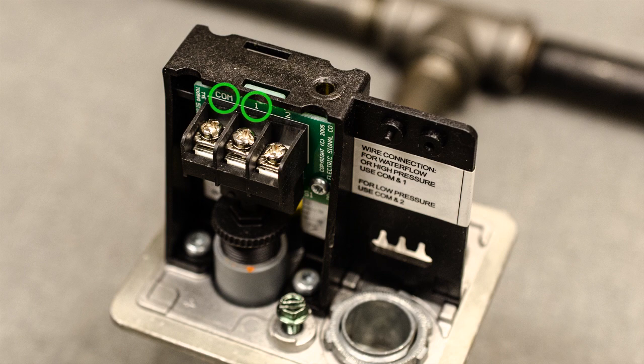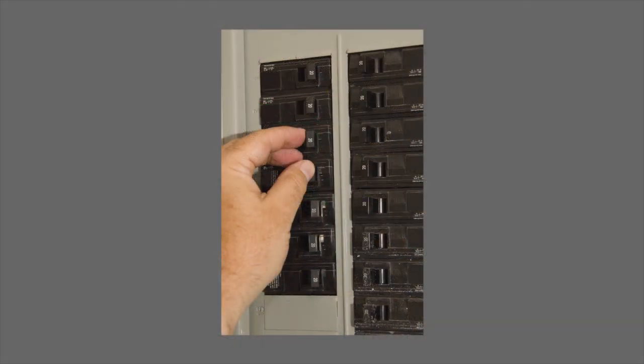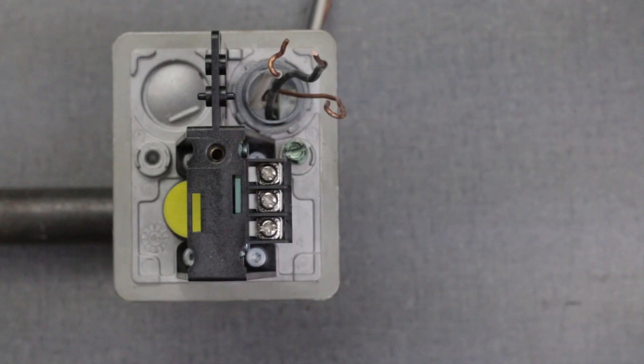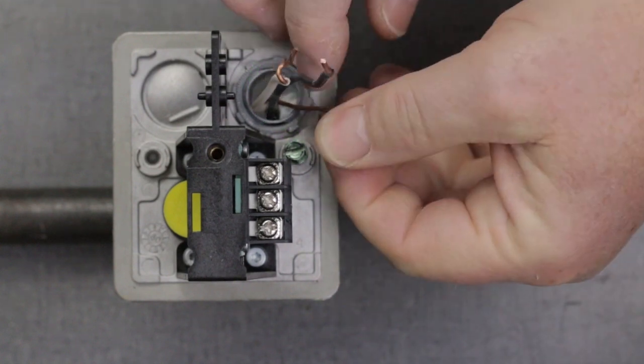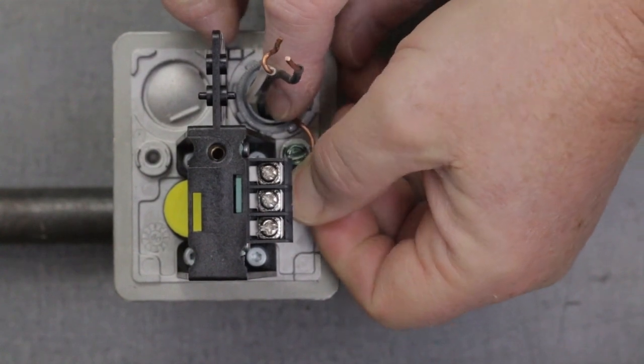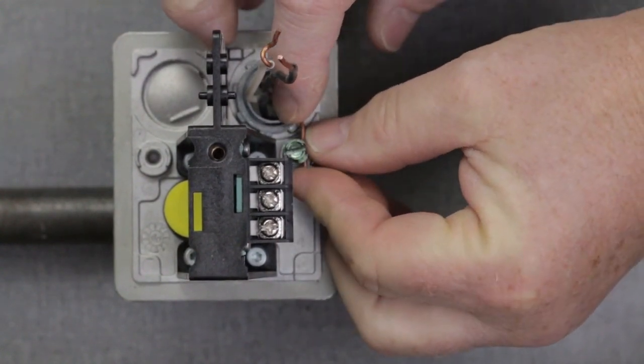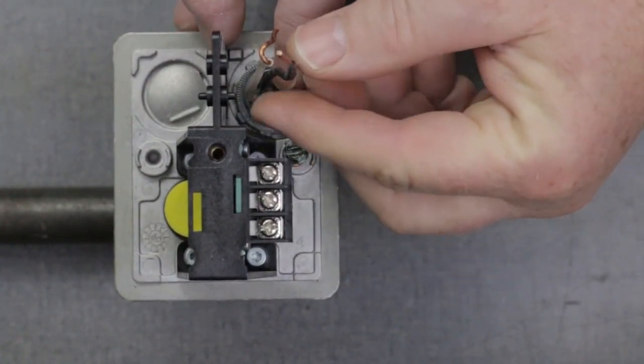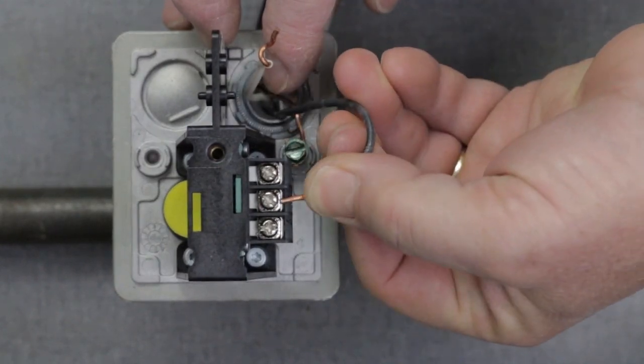These are the terminals marked COM and one. Turn off the breaker that will be used to power the bell. Pull a hot black, neutral white, and ground green or bare wire from the circuit into the pressure switch housing. Connect the ground wire to the ground screw. Connect the hot wire to terminal one.